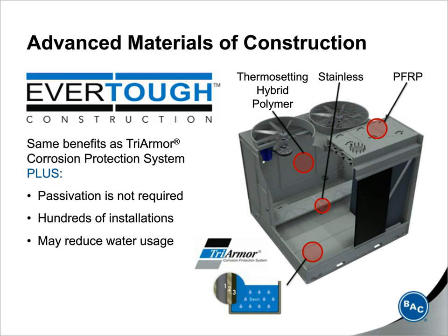Now, for even greater corrosion protection, you can add a fiberglass hot water basin. That's the distribution basin that's shown at the top here. It says PFRP. You can add that to the unit. Now, this particular unit that's shown includes a polyurethane coating in the cold water basin, the thermosetting hybrid polymer powder coating on the casing panels and the structure, and the fiberglass distribution basins.